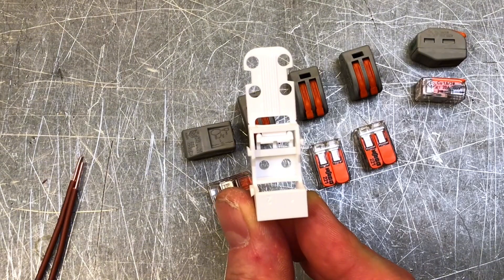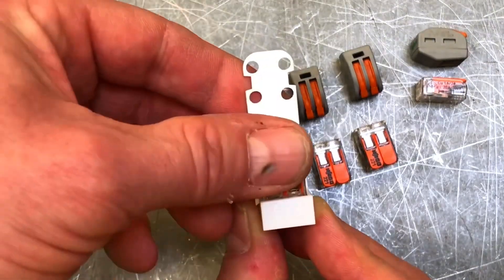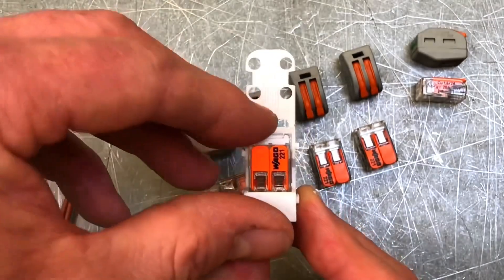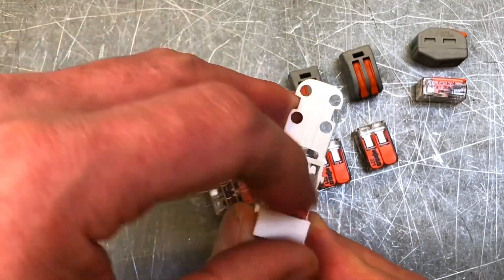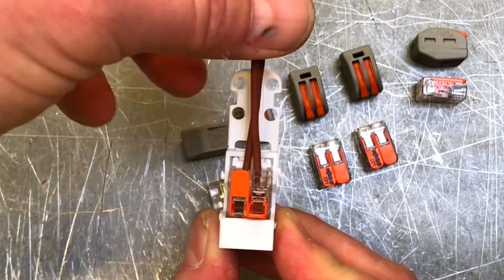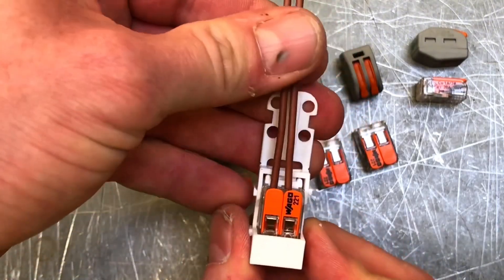Wago have brought out a mounting carrier for the 221 series. We just popped in a two conductor connector. If we're using one of these and maybe won't get looping terminals in, let's say, a light fitting, this can be mounted onto the base of the light fitting and then the connector placed in and used as a normal looping terminal. This means the actual connection won't be floating around in the light fitting.